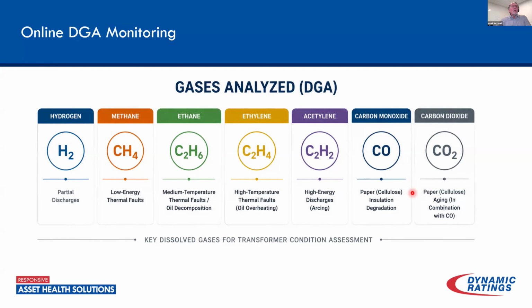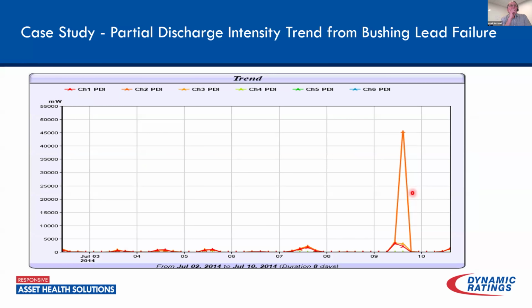Now, how is this used? This is a case study that we had, and in this situation, we had a bushing lead failure. Here they had a dynamic ratings partial discharge monitor on the unit, and you can see the partial discharge intensity values are very, very low, and were low for a long period of time, when suddenly we saw a very large spike on one phase, channel 3. At this point, the monitor was in alarm. The customer called for support and said, "Hey, what's going on?" Definitely we felt that it was new. What I thought was interesting, though, was that it came but also went very quickly, but it definitely deserves some attention.